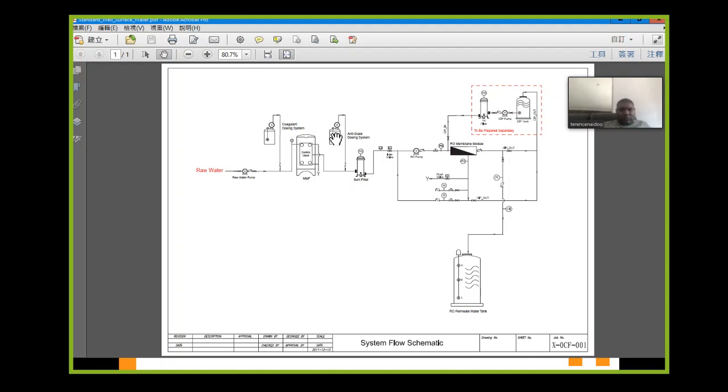Okay, let me let you know the limitation of a water softener. A water softener is only workable for feed water TDS below 1000 ppm. Maybe sometimes less than that, because it depends on the sodium chloride level in the raw water. If you have high sodium chloride in the raw water, that's salt. That will not make the water softener work, and the output of the water softener will have some hardness leak out. Okay, then anti-scalant doesn't have this issue.